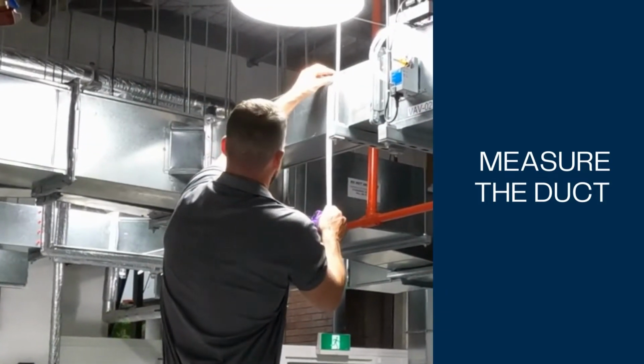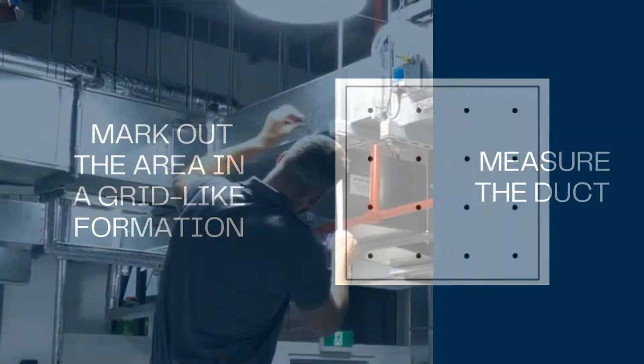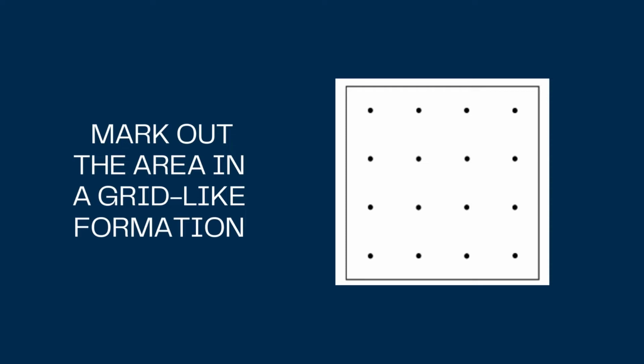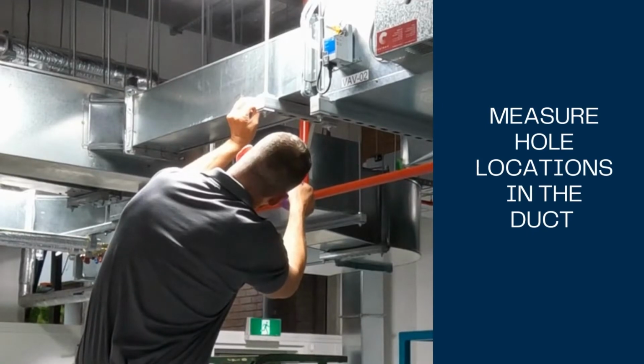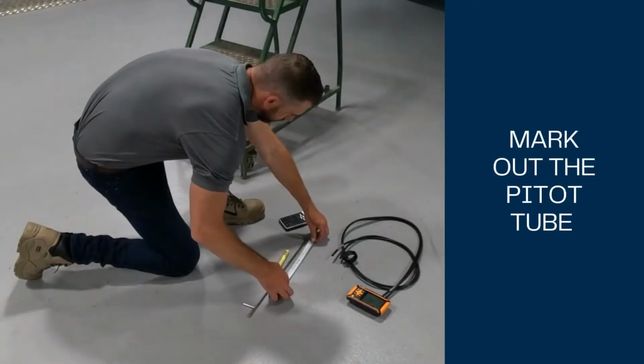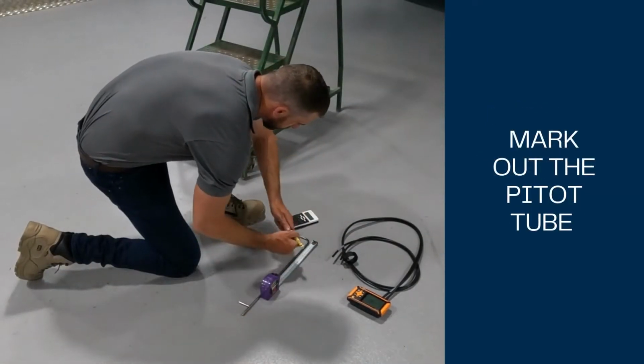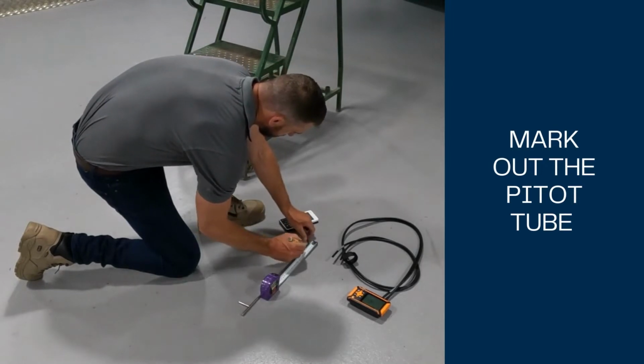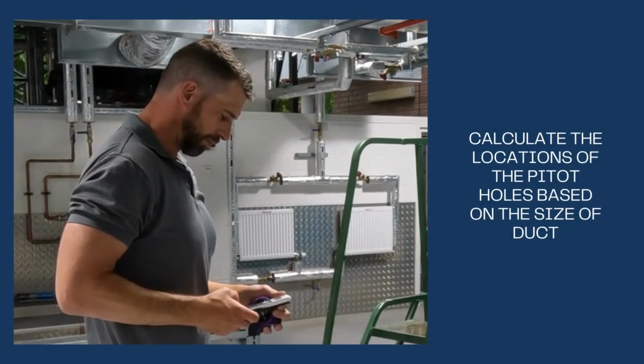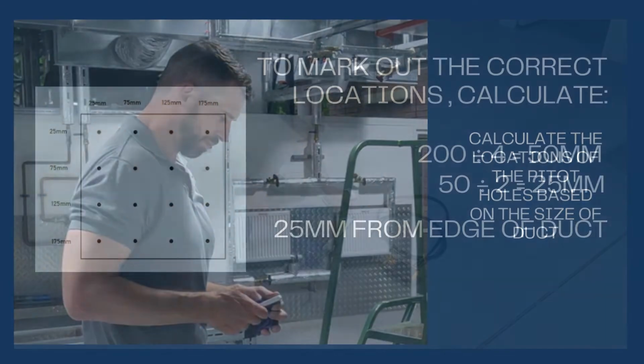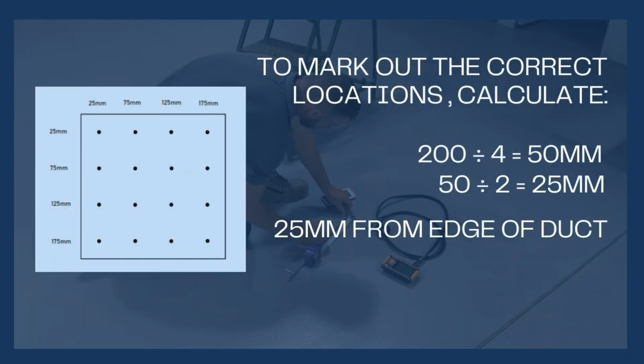First, the duct measurement is completed. In this case, the duct measures 200 by 200 millimeters. When marking pitot locations on square duct, we're aiming for a grid-like formation to ensure we are measuring an even cross-sectional area of the duct. We're aiming for a minimum of 16 readings, so we need 4 holes in the duct and 4 locations marked on the pitot tube. To get the 4 locations, we divide 200 by 4, which equates to 50 mil.